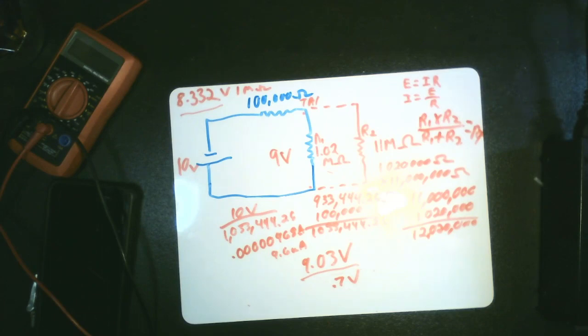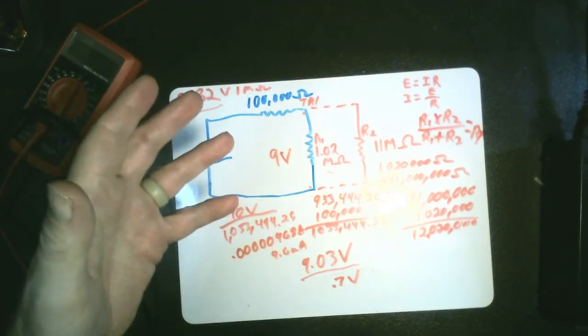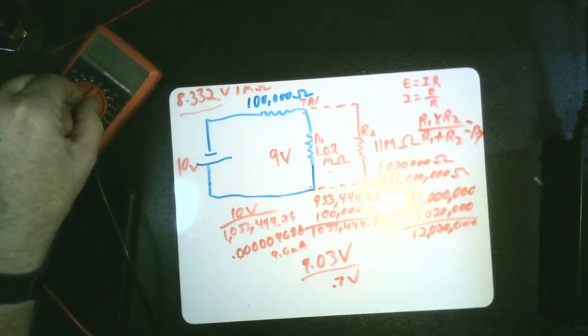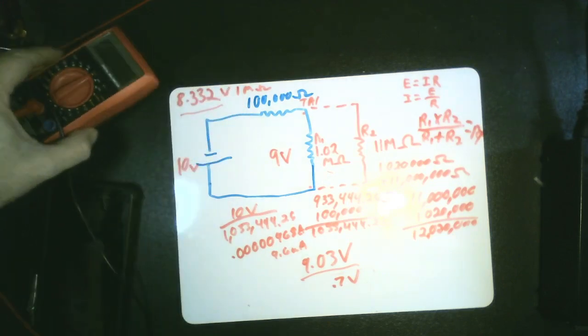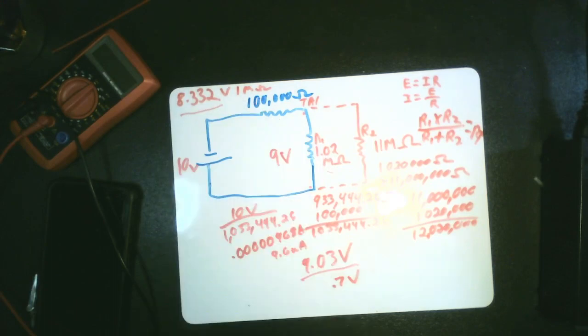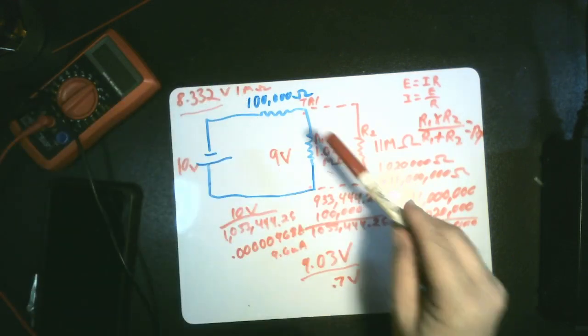And if it is an older piece of equipment and it says to use a 50,000 ohms per volt meter, well, just find out. Like on this right here, say it had a 10 volt range. We could measure that in a 10 volt range. So I said 50,000. So now 500,000 ohms is what that meter is going to have in that voltage range that you select. Well, 1 megohm is even higher than that. So you're probably not going to have exactly the same reading, but it's going to load the circuit down less. You'll probably show a higher voltage than what their service manual says. But you might just have to kind of do the math.